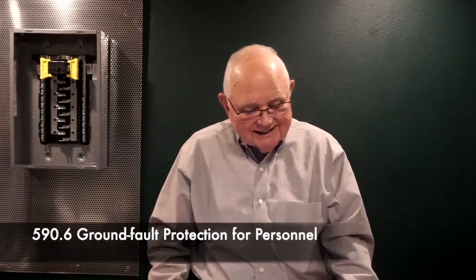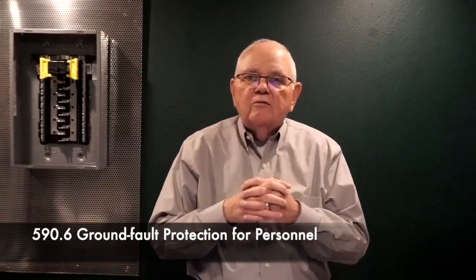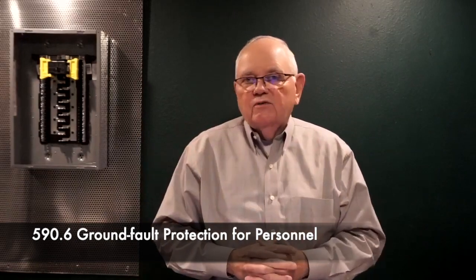And basically what it says is that we're going to do any installation, construction, maintenance, remodeling, demolition, whatever. We're going to use temporary wiring for that. We still got to meet all the requirements of the first 4 chapters. However, this one Article 590 can modify those first 4 chapters and apply the rules of Article 590. For example, if I'm going to use receptacles, 590.6, ground fault protection for personnel. And it talks about GFCI protection for receptacles.